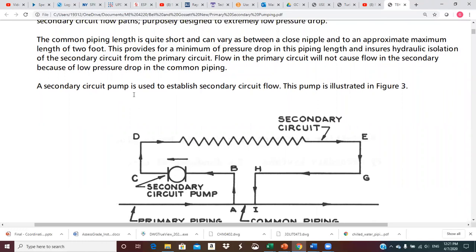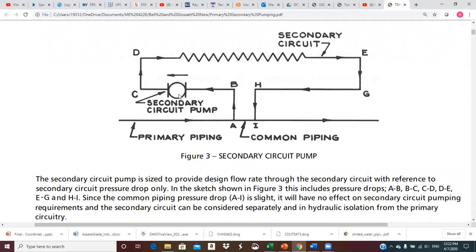The secondary circuit pump is used to establish secondary circuit flow, as illustrated in figure three. We simply put a pump into the secondary, and when we need to supply hot water to this coil, the secondary pump runs. It will pull whatever flow rate it's designed for out of the primary pipe, push it through the coil, and has enough pressure to get it back into the common pipe. This flow then mixes with what's still in the primary piping and adjusts the temperature downstream.